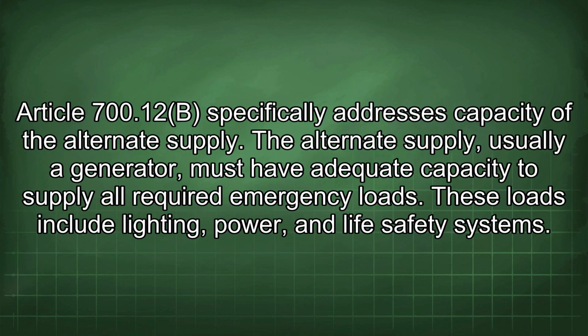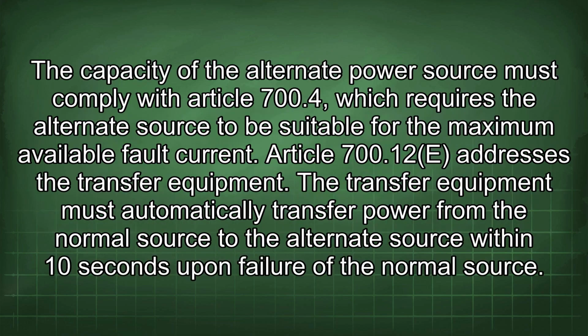Article 700.12b specifically addresses capacity of the alternate supply. The alternate supply, usually a generator, must have adequate capacity to supply all required emergency loads. These loads include lighting, power, and life safety systems. The capacity of the alternate power source must comply with Article 700.4, which requires the alternate source to be suitable for the maximum available fault current.